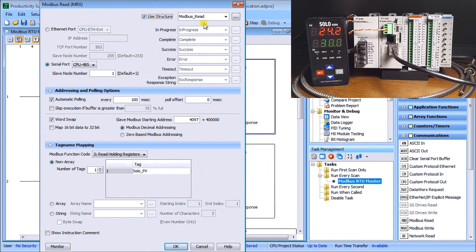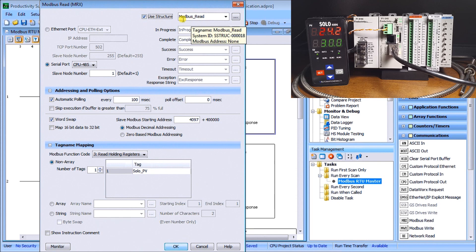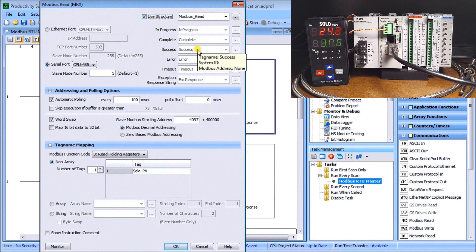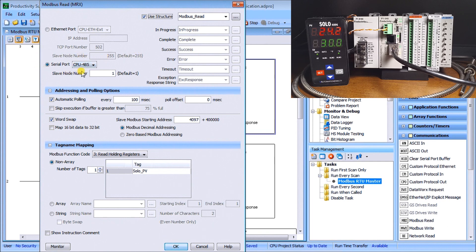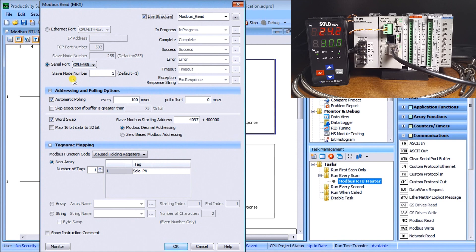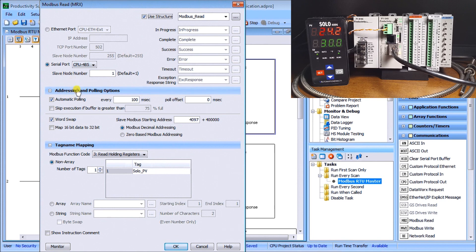We have our modbus read, we're using a structure called modbus read that sets up all these in progress, complete, success and all these other bits and flags that help us check and make sure that everything's communicating correctly. We have our serial port set for the 485 on the cpu, then we have our slave node address number one. This is the one that we're talking to, so this means that we're going to talk to the solo process temperature controller.